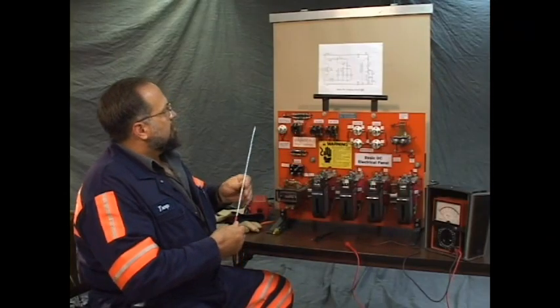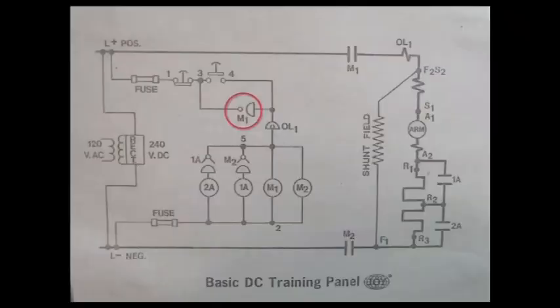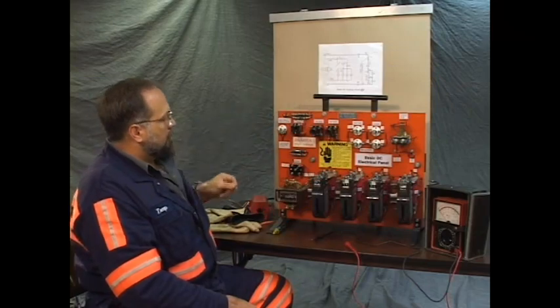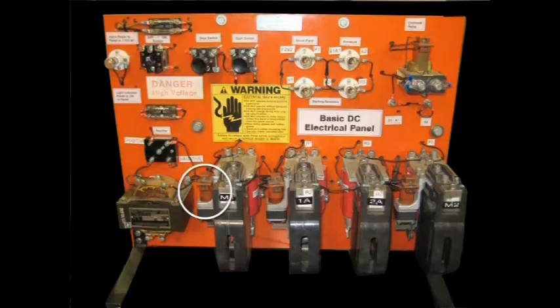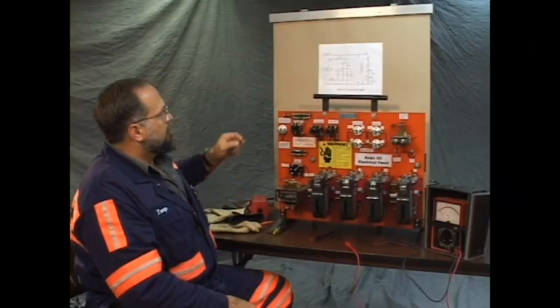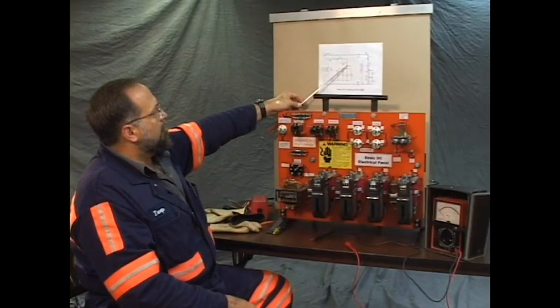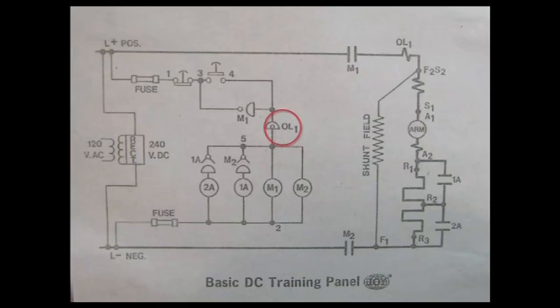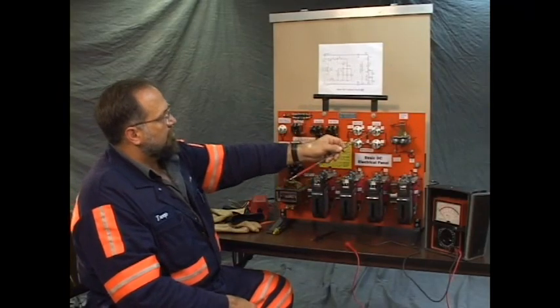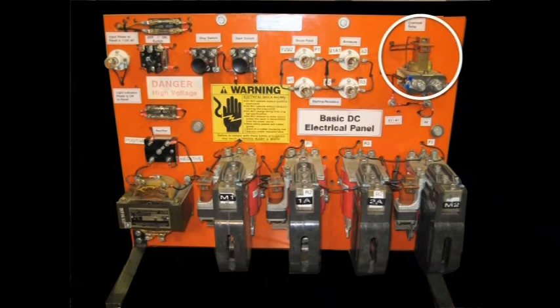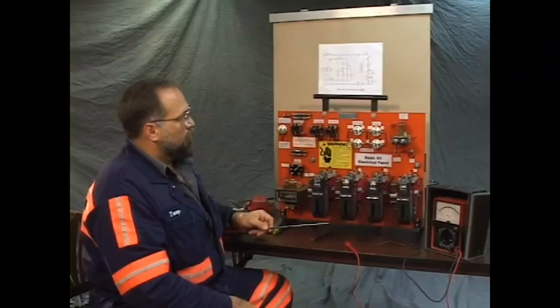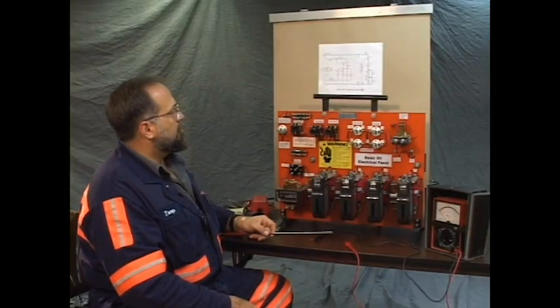Next thing on the drawing is an M1 mercury tube. M1 refers to the contactor that it's located on. That is a normally open, instantly closed mercury tube. We have a mercury overload relay, OL1. This is the tube for that. It's normally closed, instantly open.